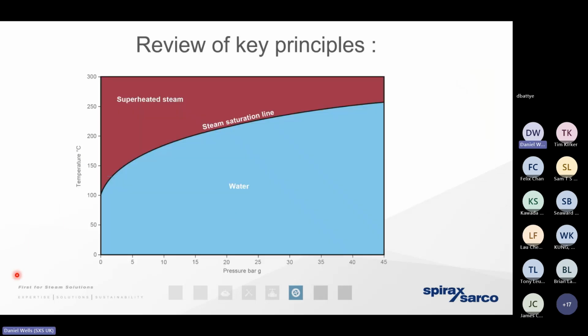And again, in previous weeks, I've mentioned that pressure-temperature relationship. At 0 bar gauge, we know that water boils at 100 degrees, and therefore the temperature of the steam is 100. But when we're generating steam under pressure, for the benefits we've already discussed, the steam's going to exist at a higher temperature. Now, we've also mentioned that when steam condenses, it gives up its energy and changes state from a gas to a liquid, but it doesn't cool down. So there's a pressure-temperature relationship that applies both to the steam and to the condensate itself. So if you think about that steam distribution pipework, if we're distributing steam at 10 bar gauge, the temperature of both the steam and the condensate is going to be 184 degrees.